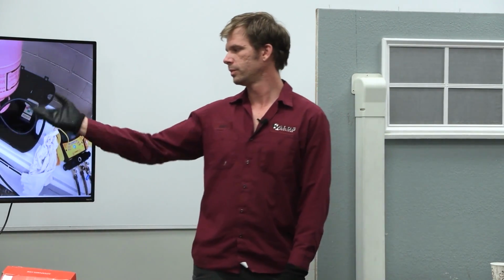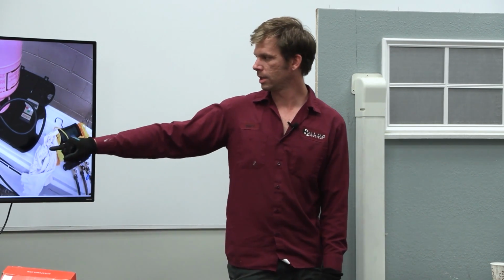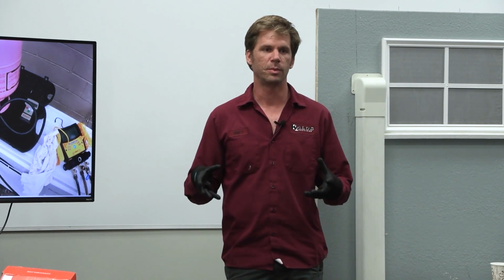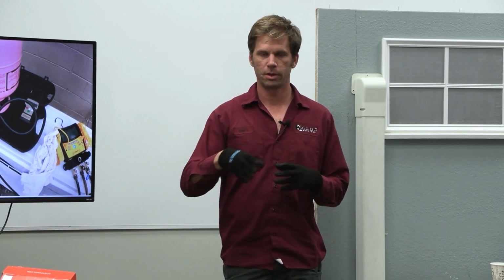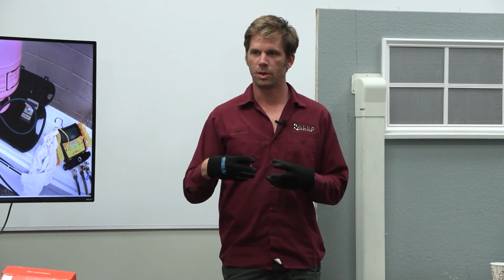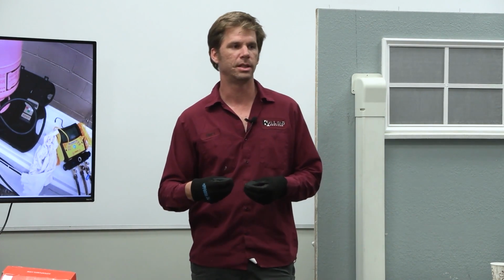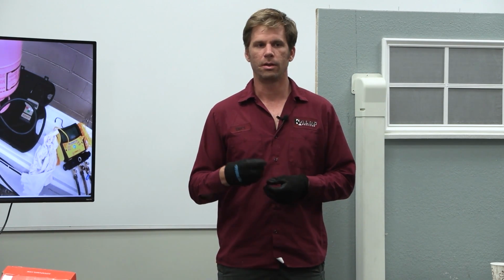So typically you want to go somewhere around the low side for pressure testing, but if you look at the manual, they'll often ask you to go even higher than that to test those flares. Put bubbles on them every time. When you put bubbles on the flare, you do a nice smooth coating on that flare, and you let it sit for a little while. If you don't see bubbles right away, you can come back to it and see if there's any active bubble action going on there on those joints.